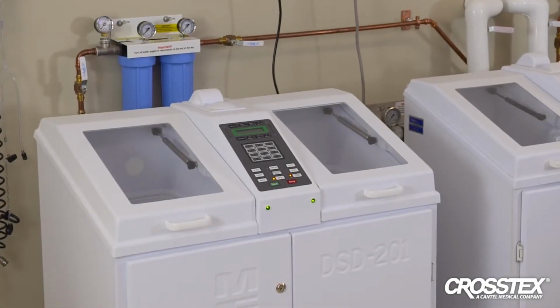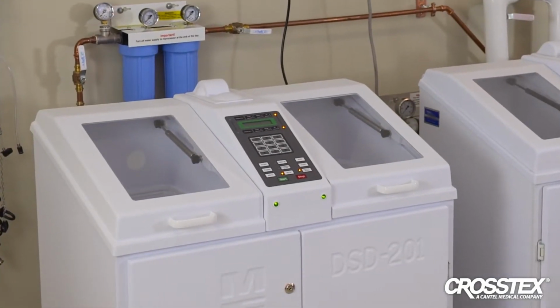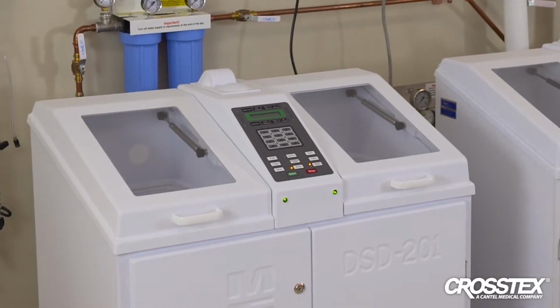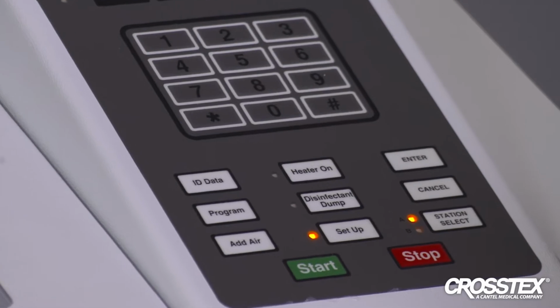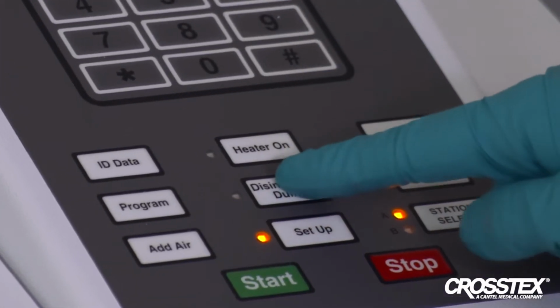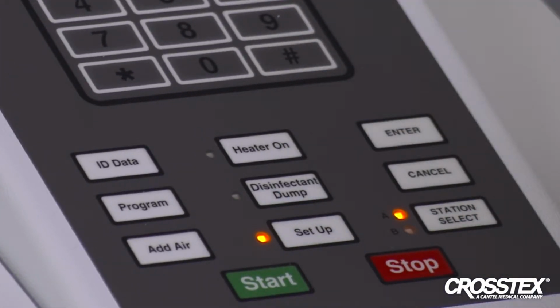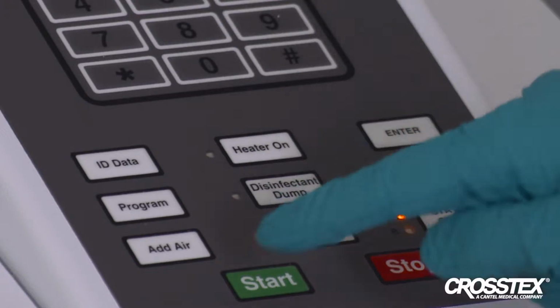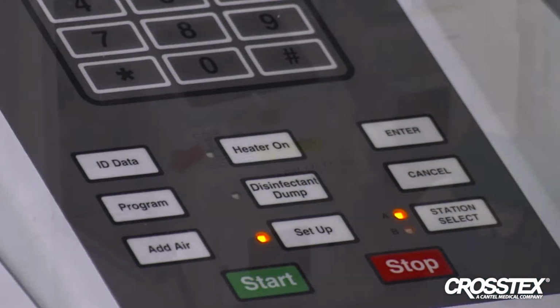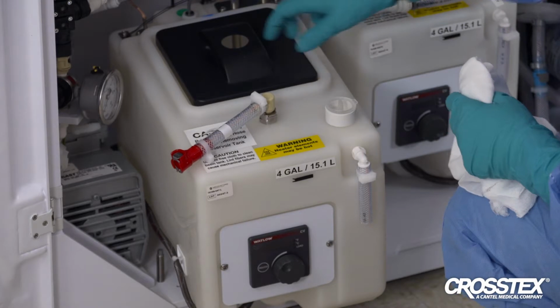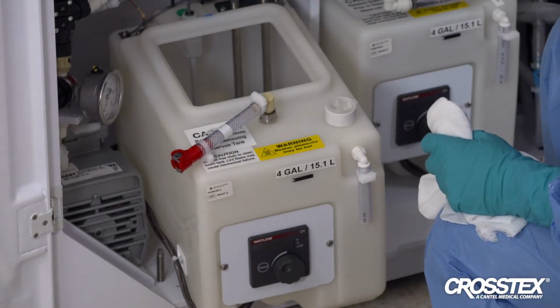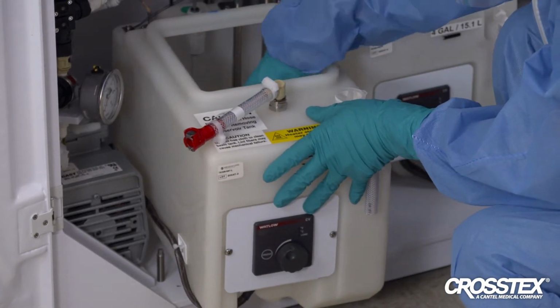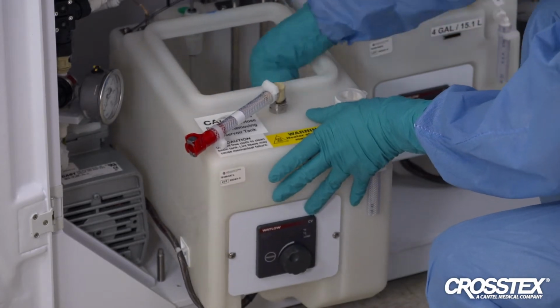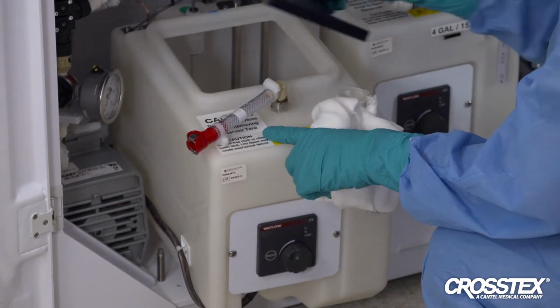To clean out when switching from one type of disinfectant to another in the Medivator's DSD reprocessor, follow these steps. Remove the existing disinfectant by evacuating the existing disinfectant from the reservoir tank. This can be done by pressing the disinfectant dump and start keys on the AER control panel. Visually ensure that the reservoir tank is empty. Remove the tank and wipe it clean with a damp, lint-free cloth. Refit the tank in the machine.